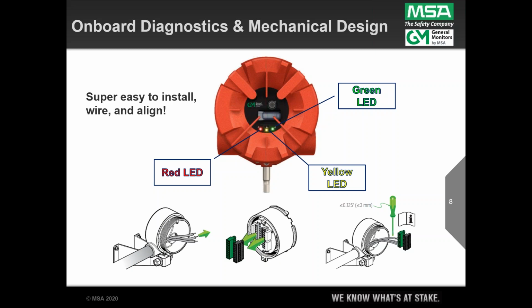As far as the installation piece, it's a nice modular design where you have a module on the inside. That's what the three images across the bottom represent. Pull the cover off, bring the cable wiring through. You can actually disconnect the Phoenix-style green terminal connectors and make your wiring connections and plug them into the module, put the module back into the bulkhead or the base of the detector housing, and then thread the cover on.